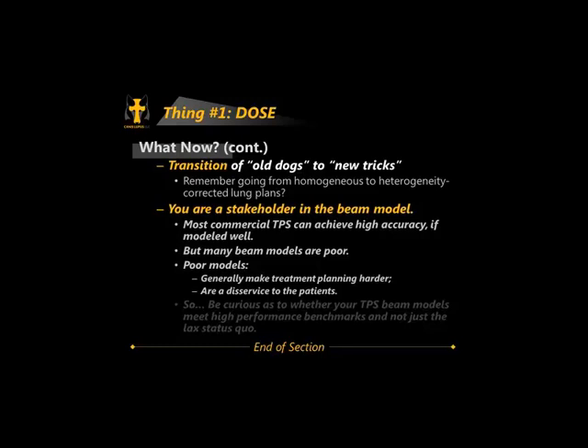You are really a stakeholder in the beam model. Your physicist's beam modeling has a direct effect on your work. There are a lot of pretty poor beam models out there — I do a lot of QA work and when I apply stringent criteria, I see this. Poor models are not rare, they generally make treatment planning harder, and they are a disservice to patients. Be cognizant and encourage your physicists — even if they think their beam model is perfect — to make it as perfect as possible and meet high performance benchmarks, not just the status quo of 3% 3mm which turns out to be very lax.